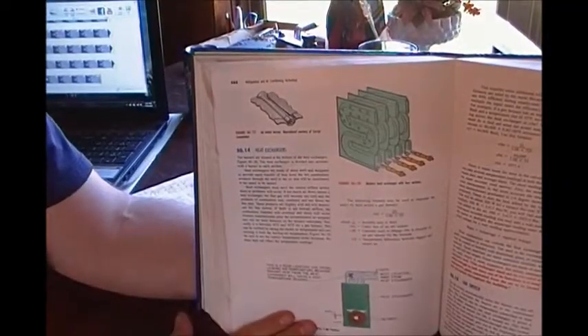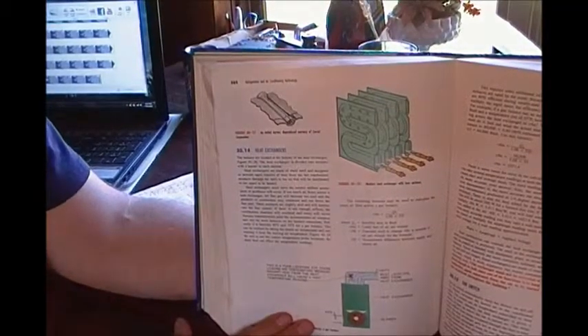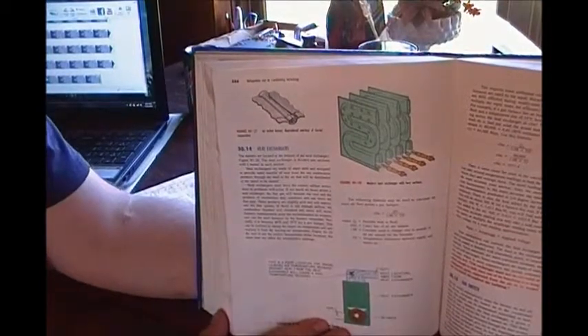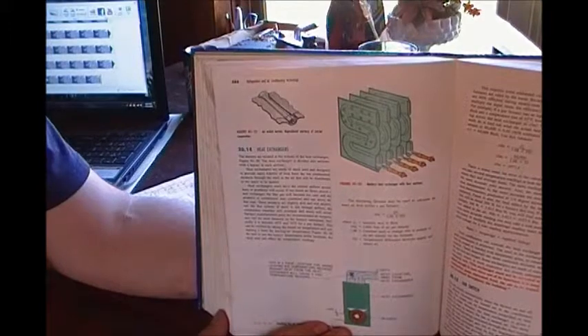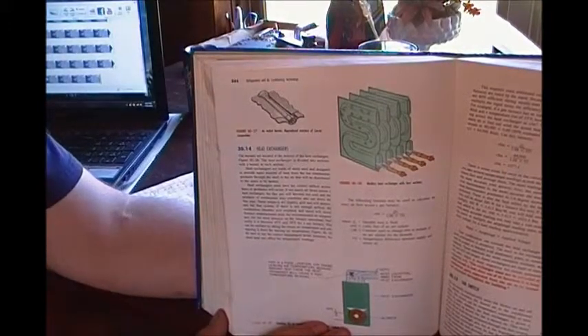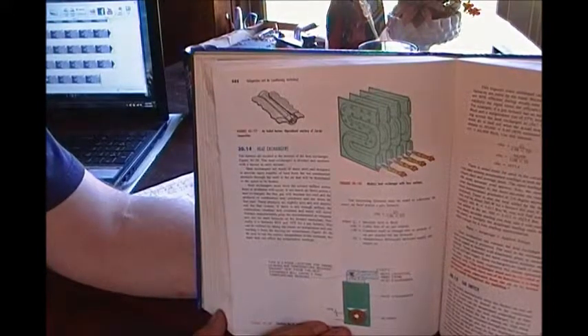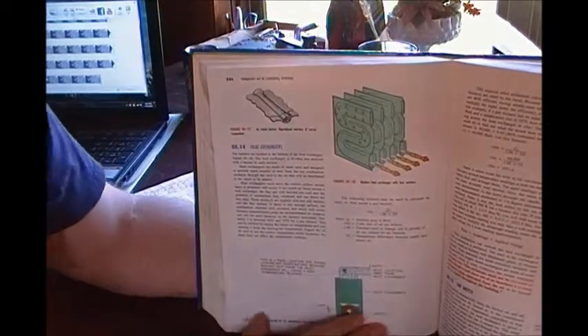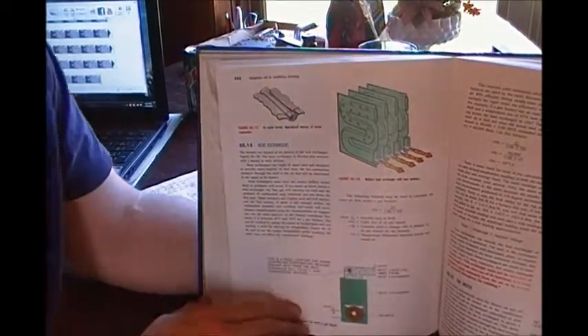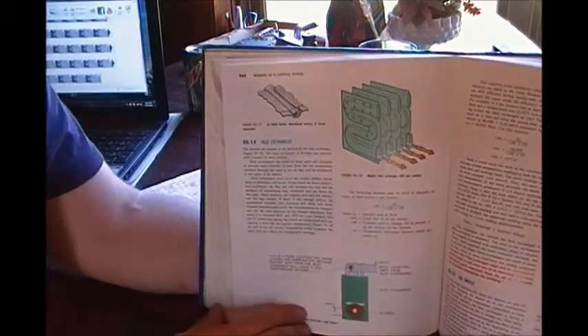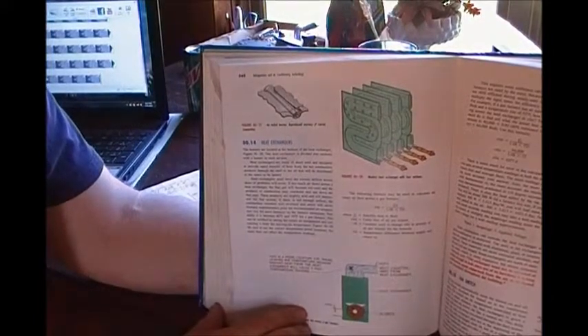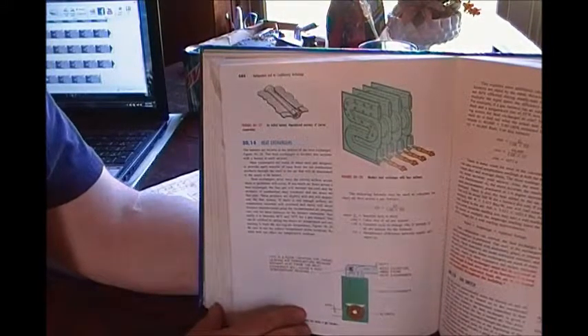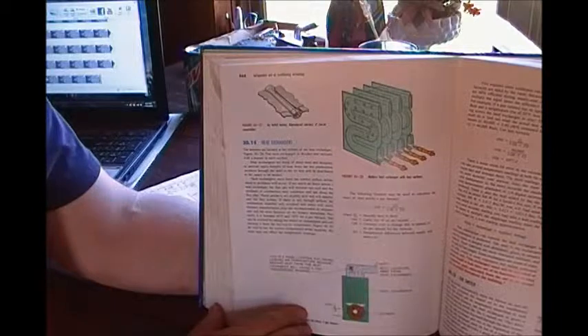Okay, so you got your 3.5 on your natural gas going to your furnace, and you've put the furnace on the highest setting for the fan, and you're blowing as much air as possible, and you're still overheating. What can be the problem? Well, here's what I found to be the problem. What'll happen is these older homes don't have enough return air, or they've put carpet over it, or they set their couches in front of it.